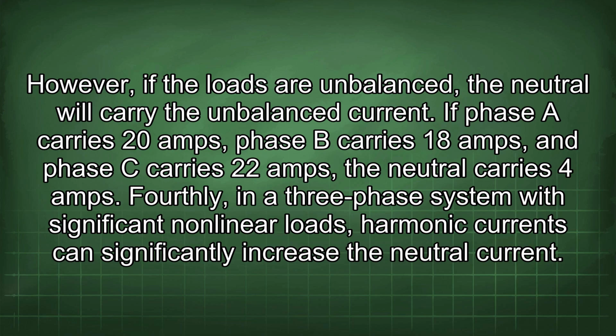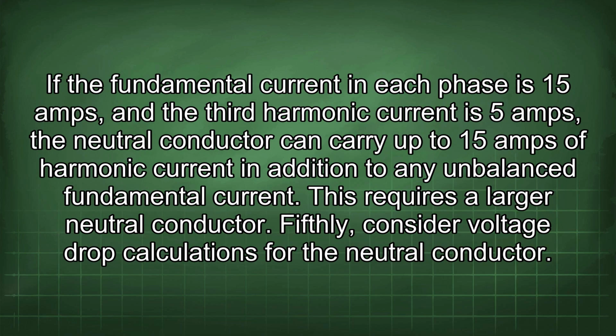Fourthly, in a three-phase system with significant nonlinear loads, harmonic currents can significantly increase the neutral current. If the fundamental current in each phase is 15 amps, and the third harmonic current is 5 amps, the neutral conductor can carry up to 15 amps of harmonic current in addition to any unbalanced fundamental current. This requires a larger neutral conductor.